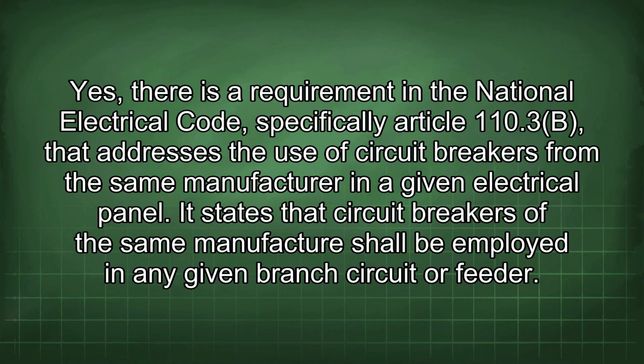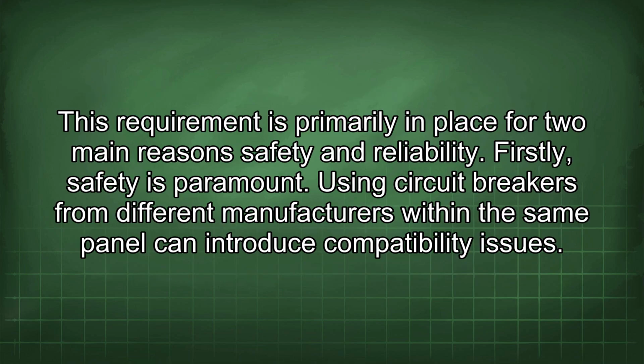Yes, there is a requirement in the National Electrical Code, specifically Article 110.3b, that addresses the use of circuit breakers from the same manufacturer in a given electrical panel. It states that circuit breakers of the same manufacturer shall be employed in any given branch circuit or feeder. This requirement is primarily in place for two main reasons: safety and reliability.